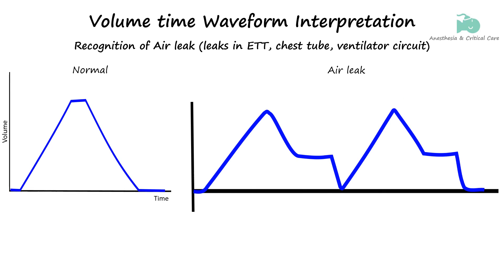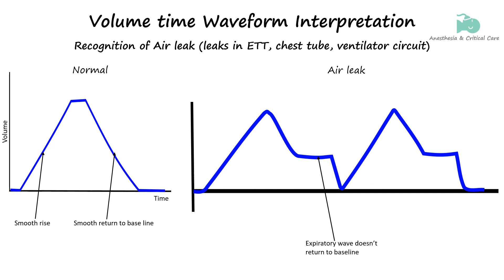An air leak in a volume-time waveform can be recognized by an abnormality in the expected pattern. Typically, in the absence of a leak, the waveform rises smoothly during inspiration, reaches a peak, and then returns to baseline during exhalation. However, when there is an air leak, the waveform will not return fully to baseline at the end of exhalation — instead, it plateaus above zero, indicating that the expected volume of air is not returning to the ventilator. The upward slope during inspiration may also be less steep, and the peak volume may be lower than expected because some air is escaping through the leak.